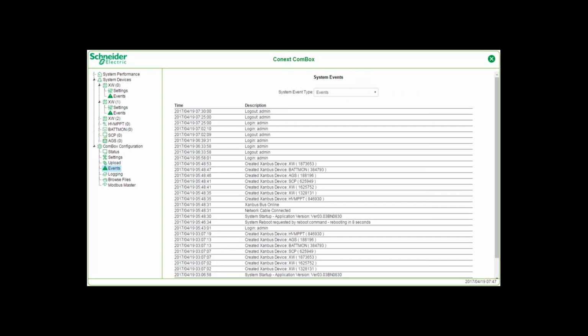Like the devices, the ComBox also has a time-stamped event log. This is from the Costa Mesa lab. We can see the system was powered up at 8 a.m., then rebooted, and followed by repeated logins by yours truly. Again, I can remote into the system anytime I want. And likewise, if you wanted that capability, Schneider Electric does recommend the use of a VPN router for security, because when you're port forwarding, you're opening up a port into your local area network to the outside world. So you want there to be a layer of security to require a login so you can access that local network externally.